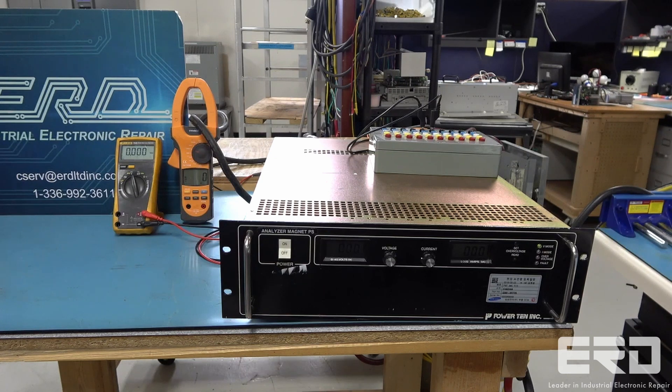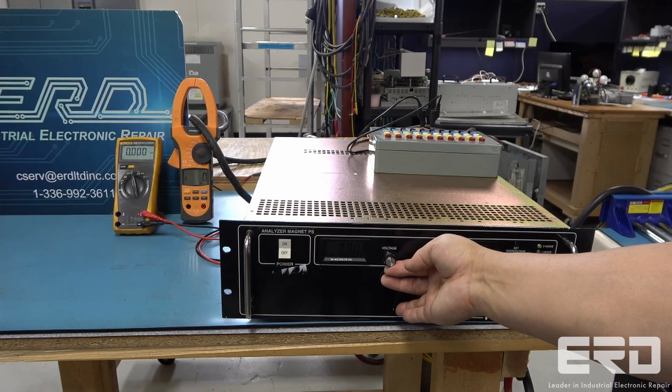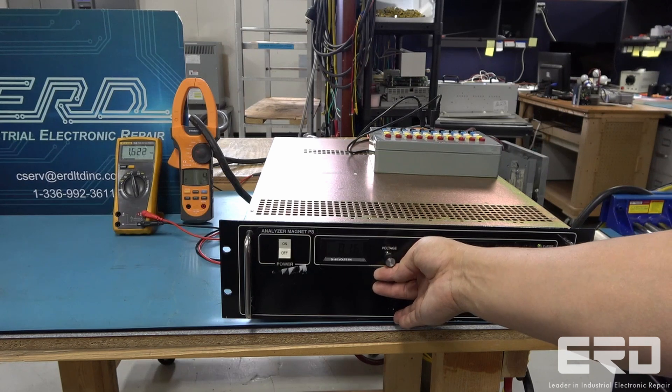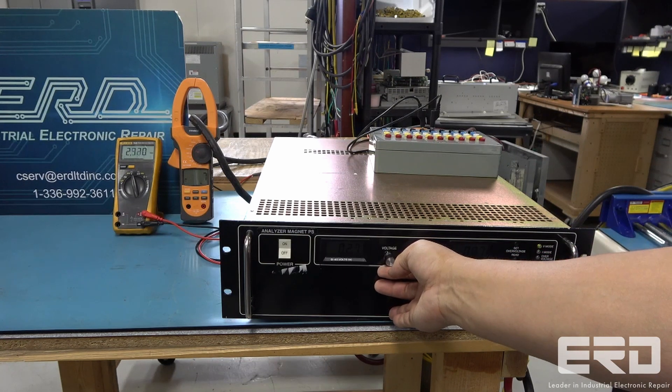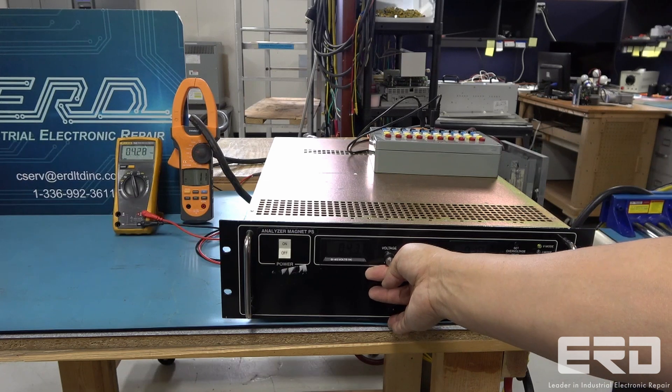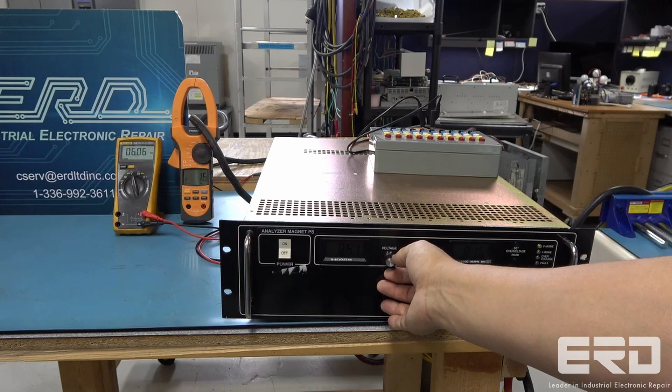This Power Ten variable DC power supply arrived from one of our semiconductor customers with a completely shorted output stage. This power supply is used for an electrostatic chuck system and a tool for making semiconductors. An electrostatic chuck is used in the handling of the wafers as they are being manufactured and does not rely on mechanically moving the wafer.